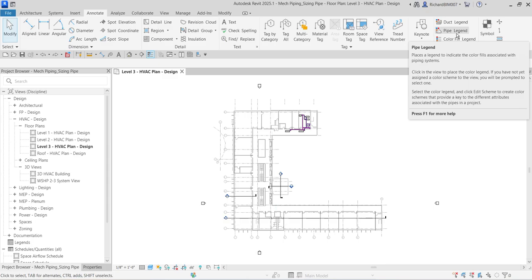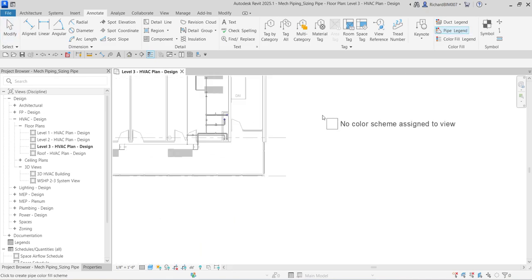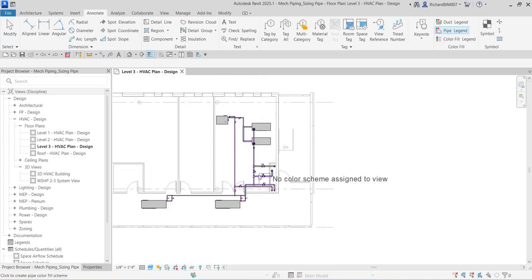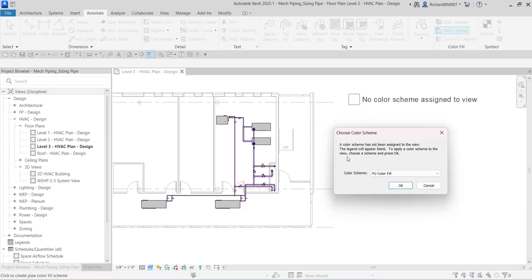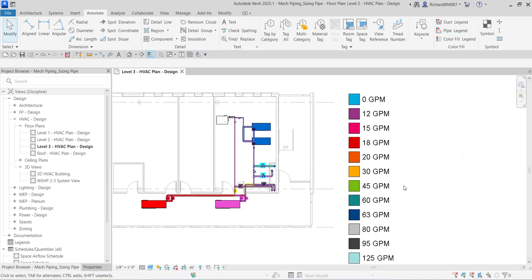We're going to use a combination of friction and velocity to size the pipes automatically. First, let's place our pipe legend. Click that option, zoom into the piping area, and place the legend. For the color scheme, select 'Pipe Color Fill Flow' — this option displays the pipes in colors based on flow value.